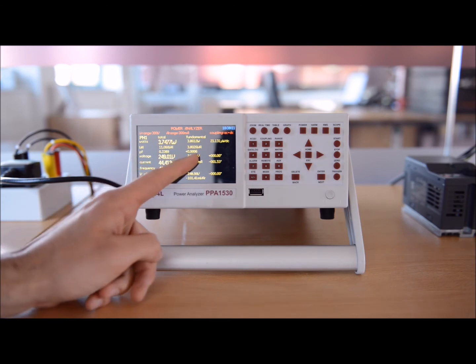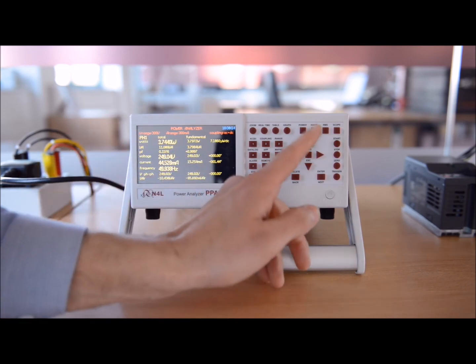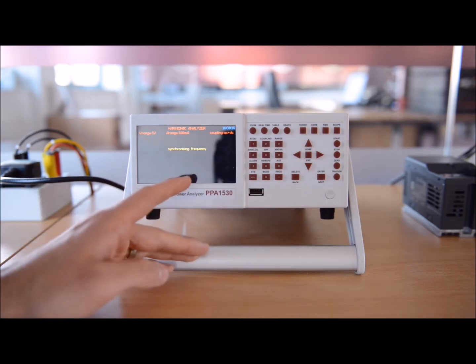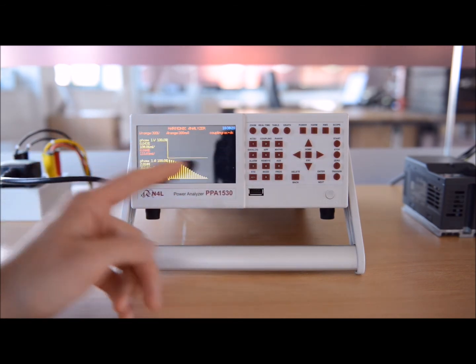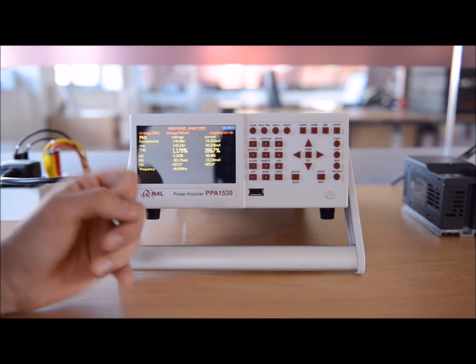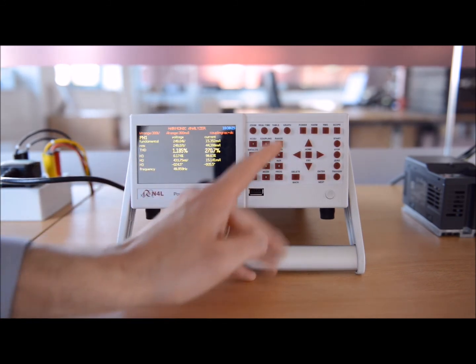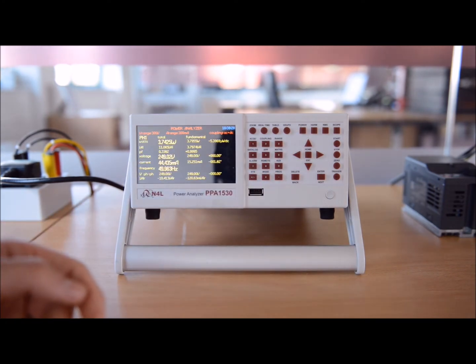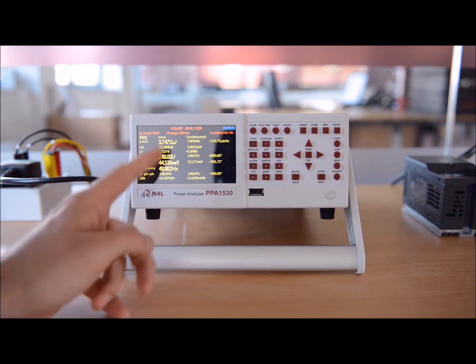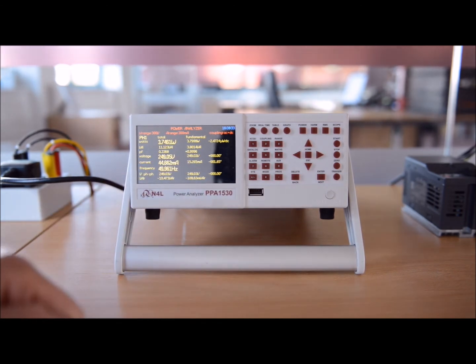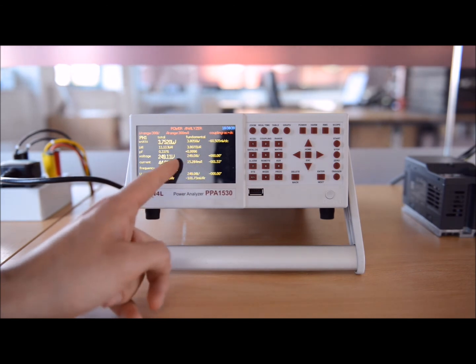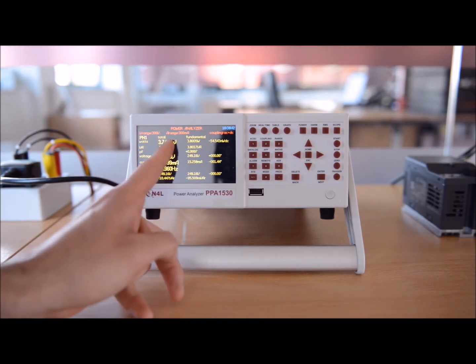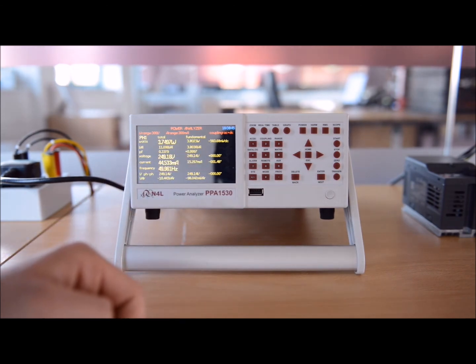Now here, what we've got, very similar numbers. That makes sense because in the harmonic menu, you can see that there's very little distortion to the voltage, which gives us an idea that the wideband RMS is going to be very similar to the fundamental, which is at 50 Hz, which is the case, only a volt different, so very little distortion there. Now, although we've got a distorted current, we actually have most of the power at the fundamental. So that's something to consider. Just because we have current wideband, it doesn't mean that we're going to have power wideband.